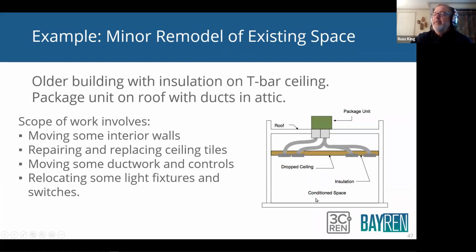They're going to move some interior walls around. They're repairing and replacing some of the ceiling tiles because they're moving interior walls around. They're going to have to replace some of the ceiling tiles. They're moving some ductwork and controls. So maybe they're adding some offices, and they have to put registers in each of the offices to make them comfortable. And they're relocating some of the light fixtures and switches. So that's the scope. So that's the first thing you have to figure out: what are they changing?